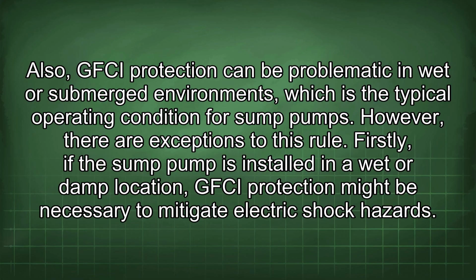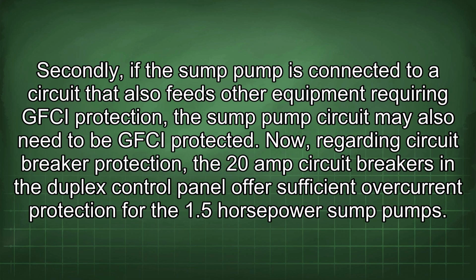Firstly, if the sump pump is installed in a wet or damp location, GFCI protection might be necessary to mitigate electric shock hazard. Secondly, if the sump pump is connected to a circuit that also feeds other equipment requiring GFCI protection, the sump pump circuit may also need to be GFCI protected.